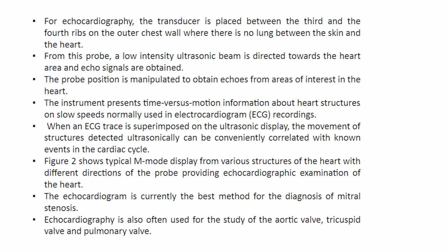The instrument presents time versus motion information about heart structure at slow speeds normally used in electrocardiogram recordings. When an ECG trace is superimposed on the ultrasonic display, the movement of structures detected ultrasonically can be conveniently correlated with the known events in the cardiac cycle.